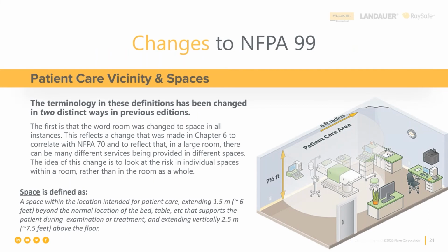Other changes: patient care vicinity and spaces. Where is this electromedical device in your hospital? The terminology in this definition has been changed in two distinct ways from previous editions of NFPA 99. The first is that the word room has changed to space in all instances. And this reflects a change that was made in Chapter 6 of NFPA 99, NFPA 70, to reflect that in a large room, like an operating room or a large treatment area, there may be different locations for the medical equipment, and you need to make the tests in all of those places.